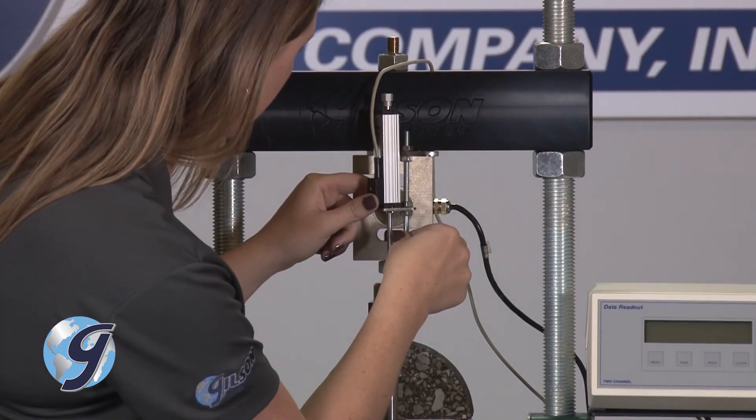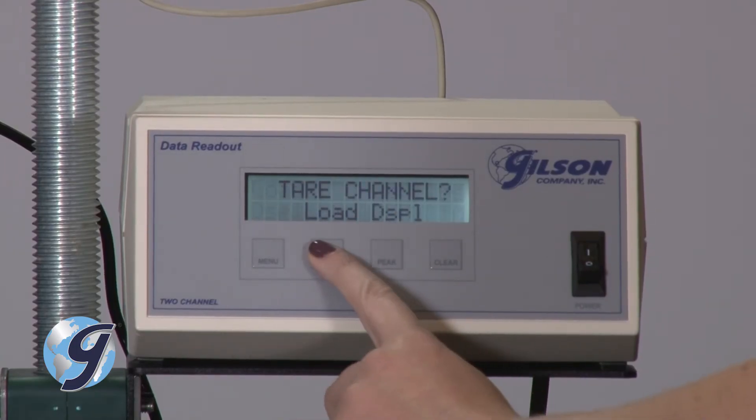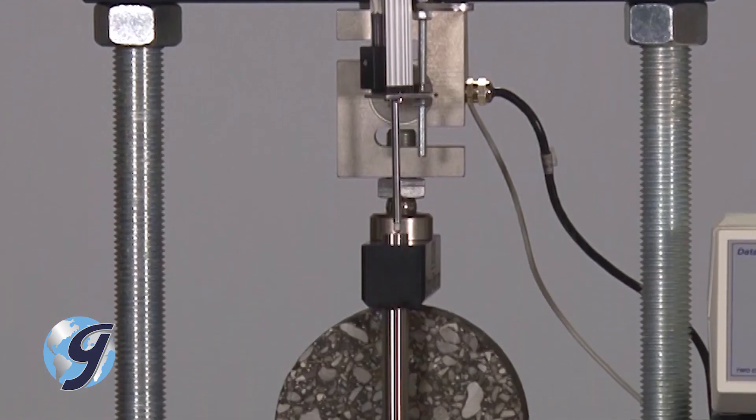Next, seat the LVDT on the vertical guide rod of the SCB fixture. Next, tare both the load cell and the LVDT. Now, you are ready to begin the test.